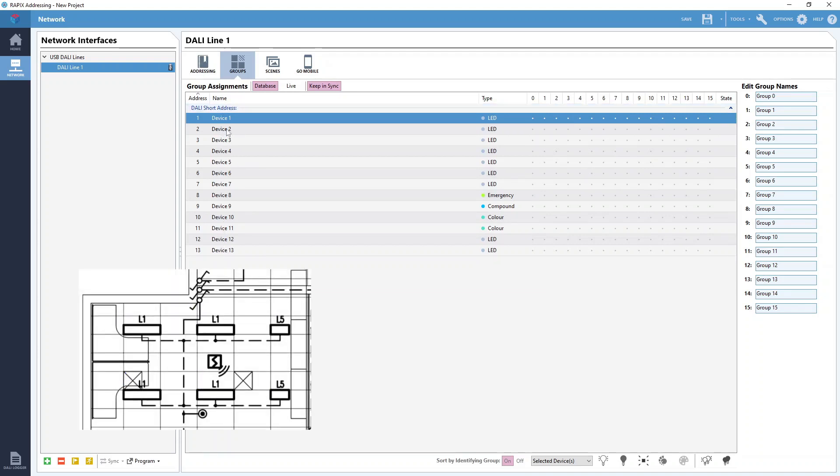We can see all our DALI devices still listed down the left here. Our available DALI groups are listed across the top up here. Each DALI line has 16 DALI groups available to it numbered from 0 to 15. And each DALI device can be a member of as many or as few DALI groups as required.